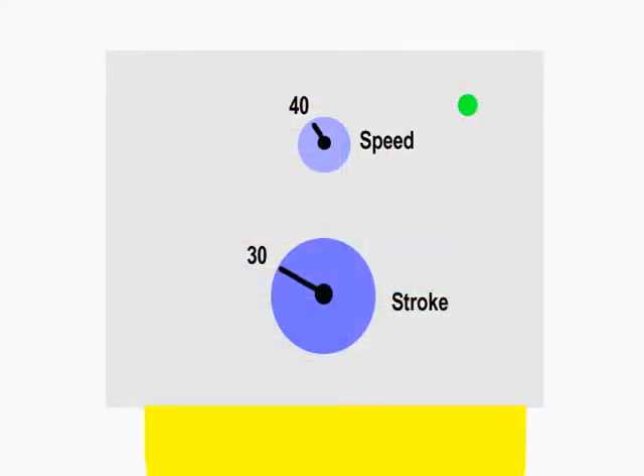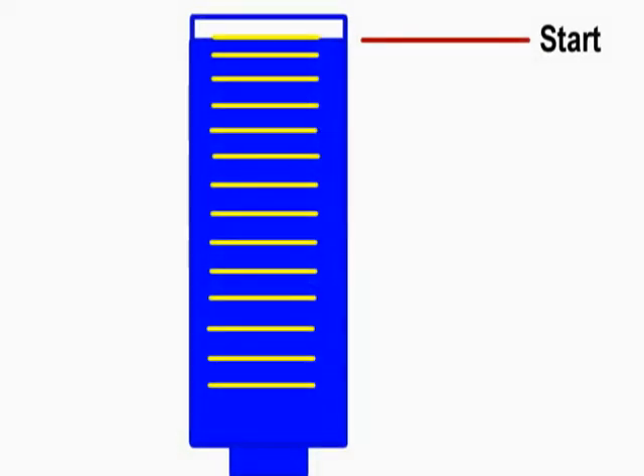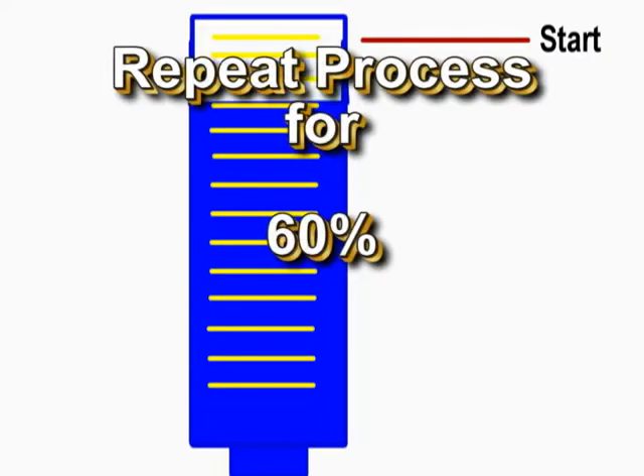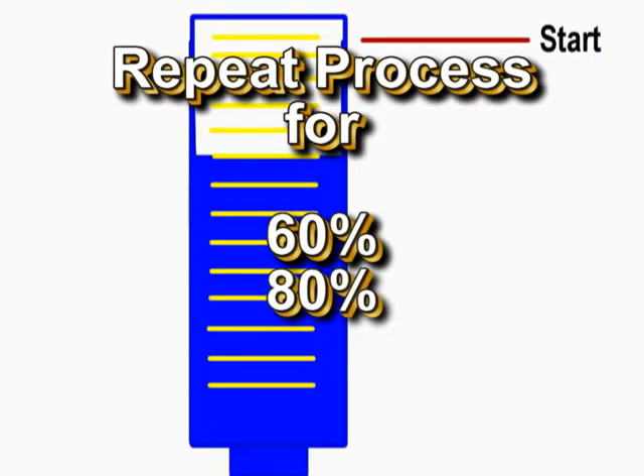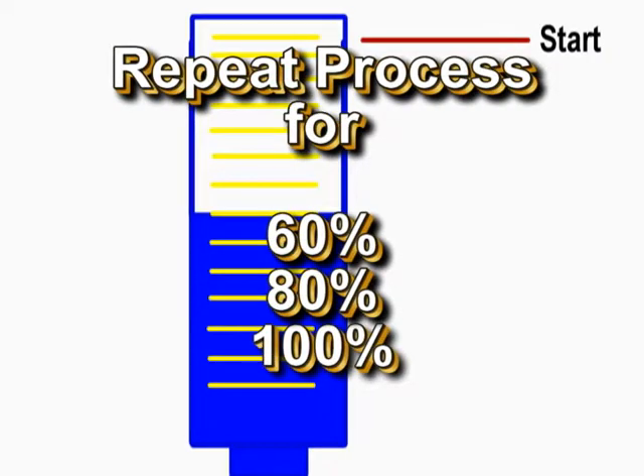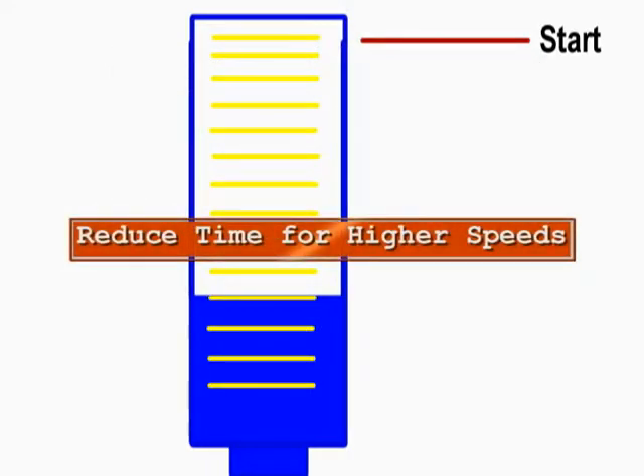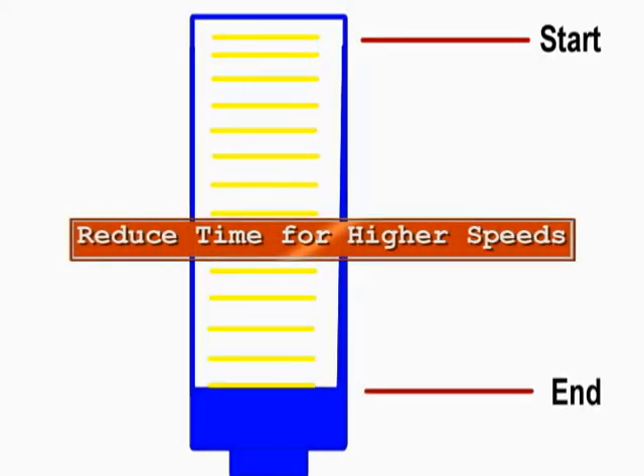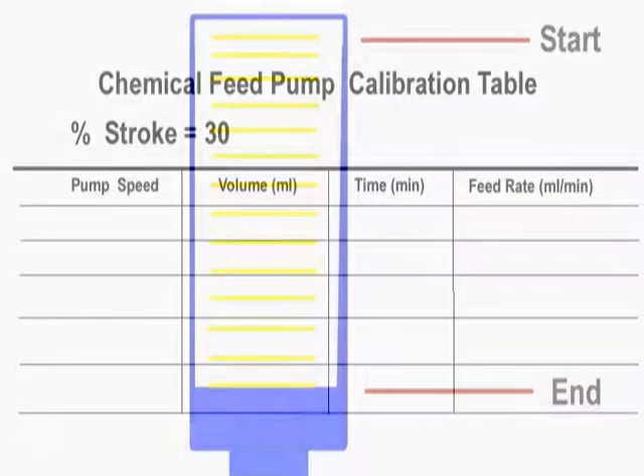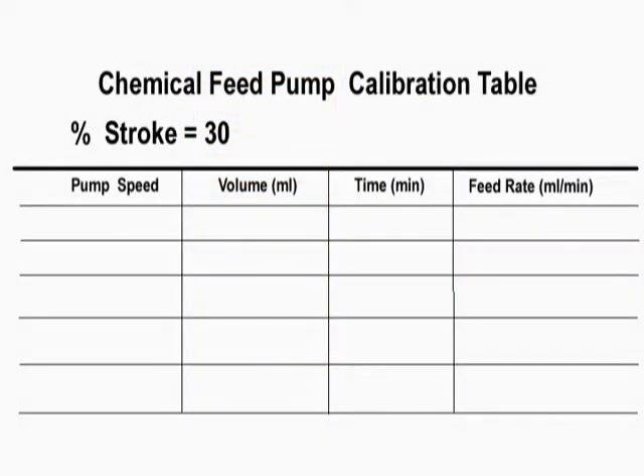Next, set the pump speed to 40 while keeping the stroke at 30 percent, refill the calibration tube, and time for two minutes. The process should be repeated for 60, 80, and 100 percent speeds. The time can be reduced to one minute for the higher speed settings. The results should be recorded on a table.